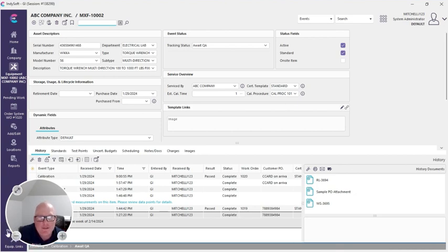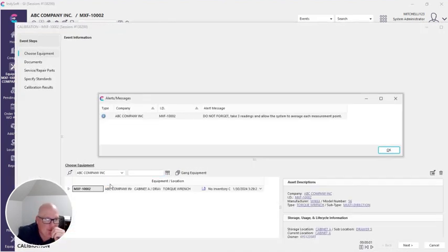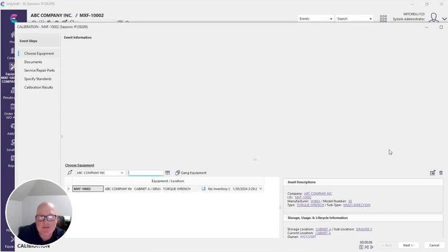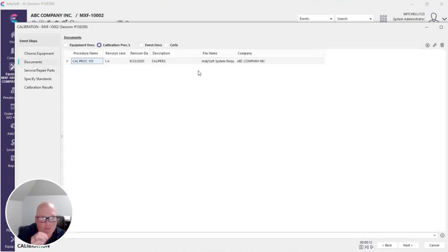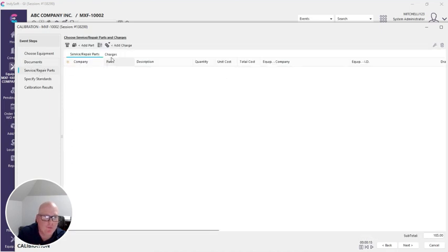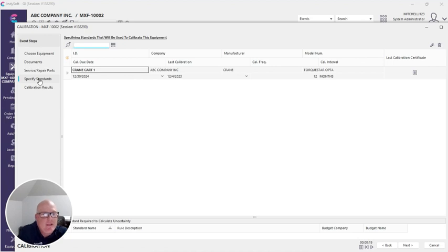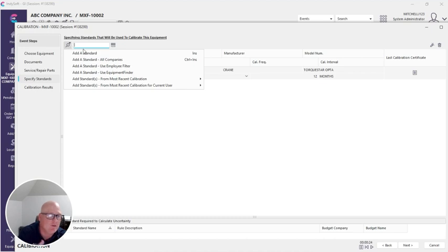Let's say that we're in the middle of a calibration event, and I just have a little pop-up message there about don't forget to take my readings or my averages. When you go through the event, we always have our who, what, when, where. We have our calibration procedures that are available. We have labor repair cost if you're utilizing that. But as we navigate over to our specify standards, we all know there's a variety of ways you can add your standards in. You can do it by an employee filter or by some of our hotkeys for the same standards that you used last year.